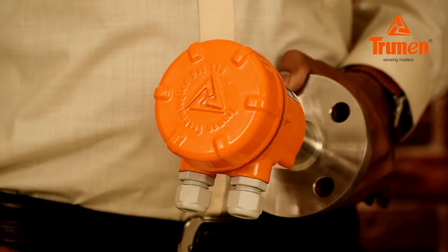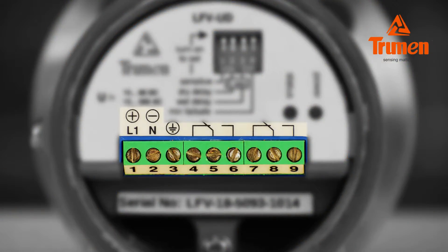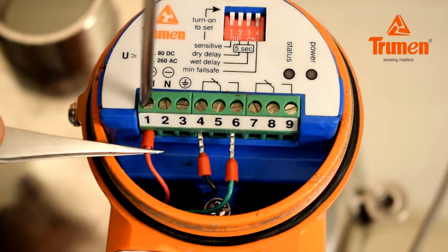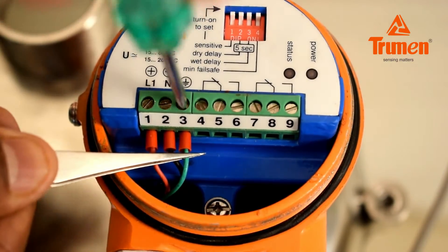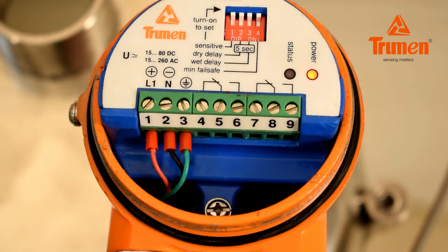The Trumen LFV is very easy to operate. Open the cover and you can see nine terminals. Terminals 1, 2, and 3 are for auxiliary power supply; terminals 4, 5, 6 and 7, 8, 9 are for relay output. Connect the power supply — either 15 to 80 volt DC or 15 to 260 volt AC — on terminals 1 and 2, and plant earth on terminal number 3. Then switch on the power.